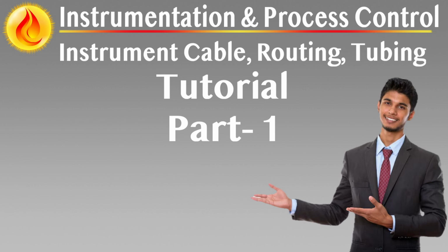Cabling for special instrument applications, devices operating outside the conventional 4 to 20 mA signal standard, such as ultrasonic meters, magnetic flow transmitters, vibration probes, or multiplexed analyzer systems, require special consideration for cabling and earthing. These applications may include unusual voltage or frequency characteristics, which dictate custom shielded, impedance matched, or low loss cable designs.